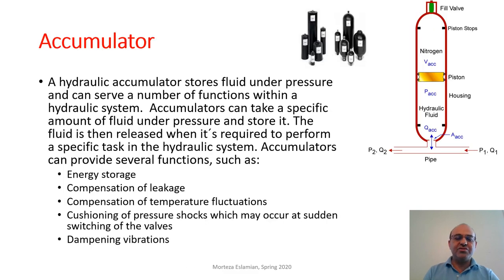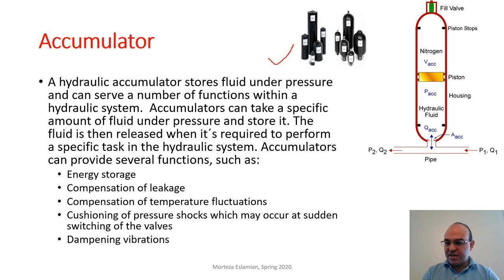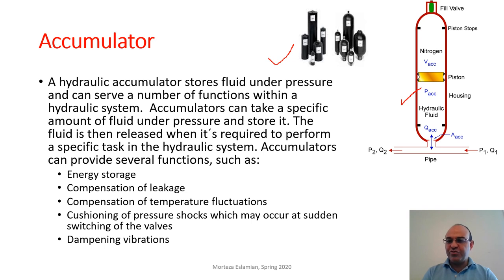One last important thing to discuss in this section is the accumulator — a component of the pump fluid loop. A hydraulic accumulator stores fluid under pressure — it looks like a cylinder. The hydraulic fluid is the same as the loop fluid, for instance methanol, ethanol, or ammonia, and it is pressurized by a gas such as nitrogen, with a frictionless piston between them.